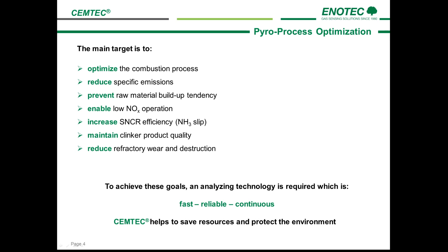Why fast? Because it's important to know what is happening in the kiln as soon as possible in order to react to changes. Reliable, because reducing maintenance and the accompanying costs is necessary. And continuous, because only with continuous measurements can the process be optimized. Some manufacturers claim to have a continuous measurement but this is not the case — kiln inlet probes are often retracted for manual cleaning, which is both dangerous and time consuming. Additionally, if the ingress of dust into the probe is high, regular purging is required, and during purging, process measurements aren't possible. The true definition of continuous measurement in the kiln is 24/7: the probe stays in the process for 24 hours and is retracted once a day purely for precautionary reasons.